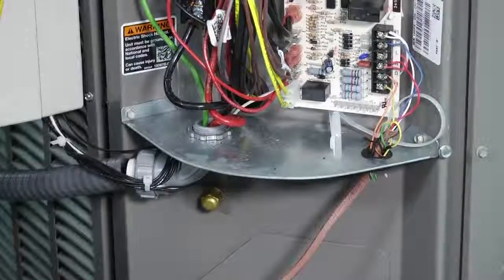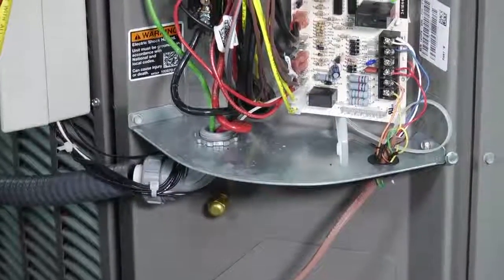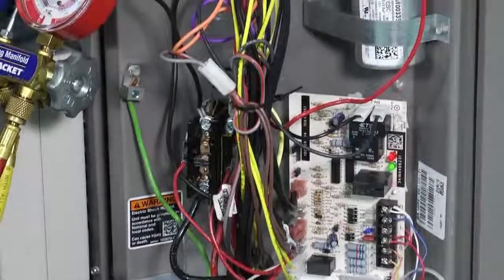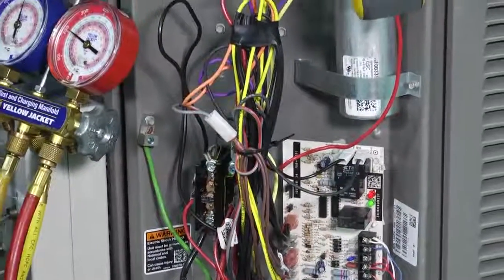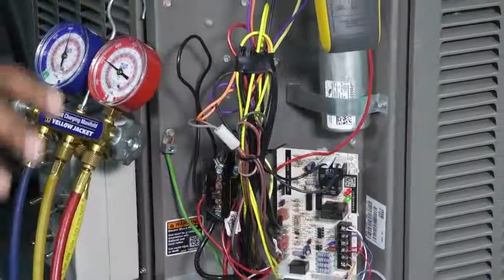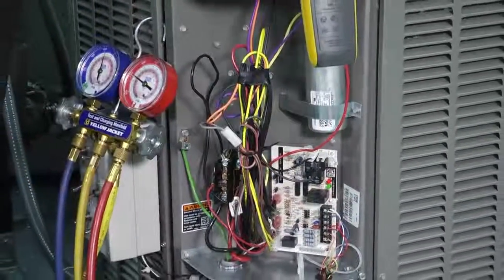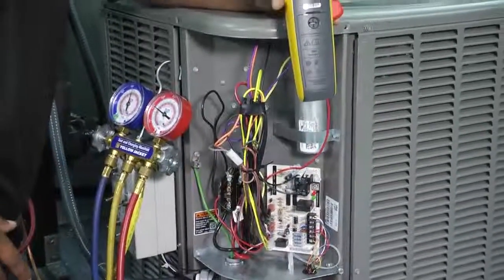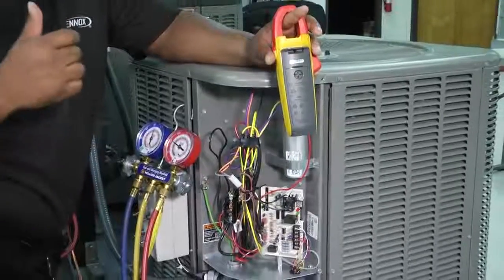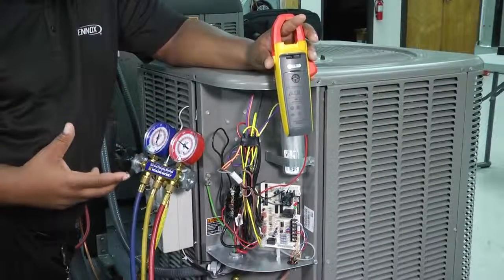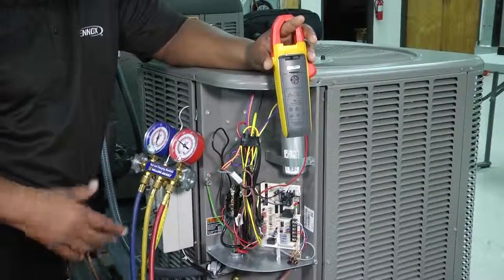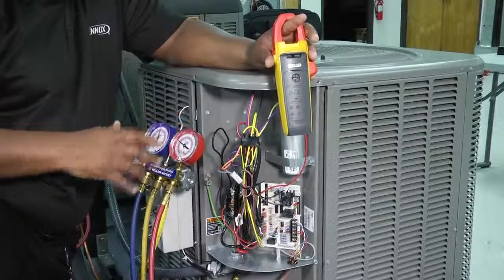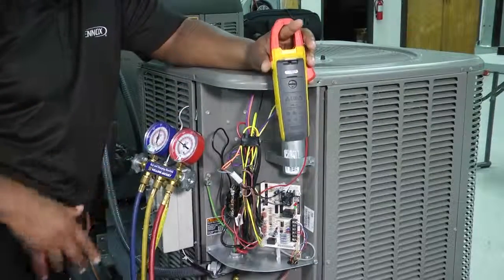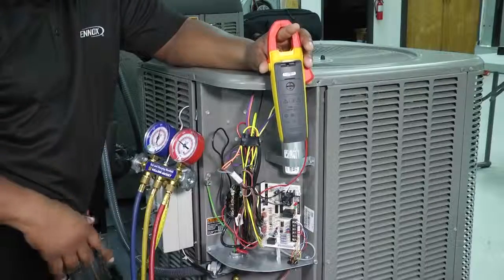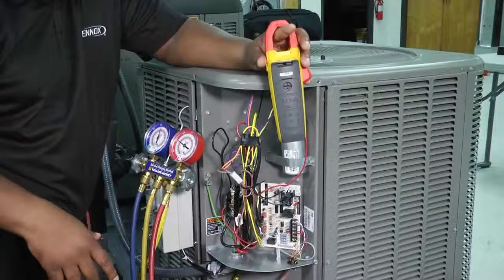So after we've cleaned everything, we've checked all of our components. Remember, there's some amp draws and different things like that to make sure our motors are working within tolerance, to ensure that our condenser unit on the AC side and our matching evaporator coil are all healthy, that they're working great, and that our homeowner is going to be comfortable in their house. These just cover a few things that we need to check, not necessarily all of them, and depending on your company and where you work, you guys might do something a little different.